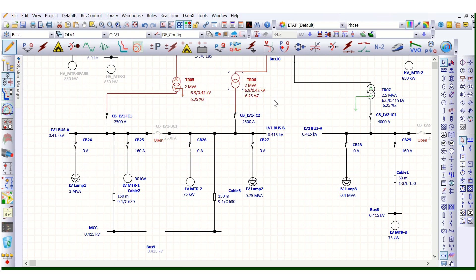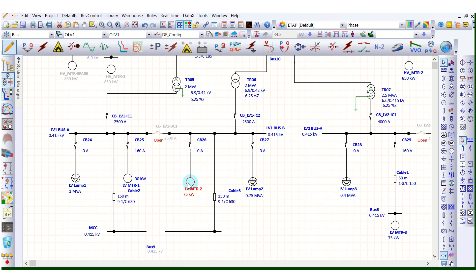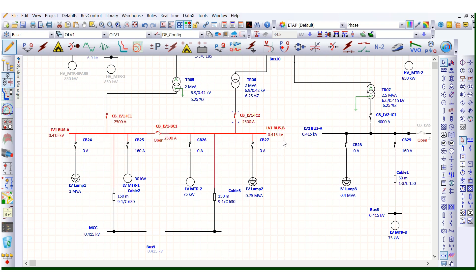We need to consider where the transformers will be located. The load center is defined as the location where the utility requirement is highest — where more than 60–70% of the total power delivered from the two transformers is utilized. For example, if large LV motors of 90 kW, 75 kW, or 132 kW are all connected in this area, then from an electrical standpoint, a PMCC must be installed in this area along with the two distribution transformers.